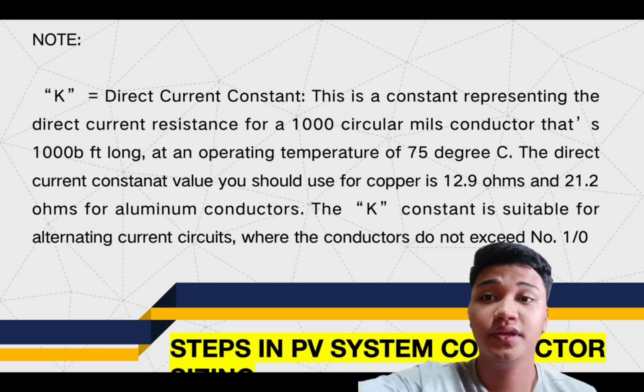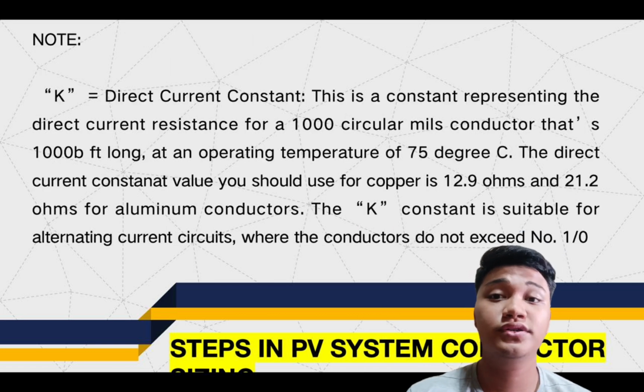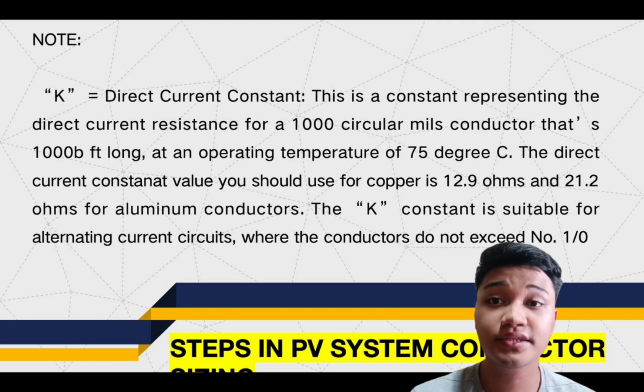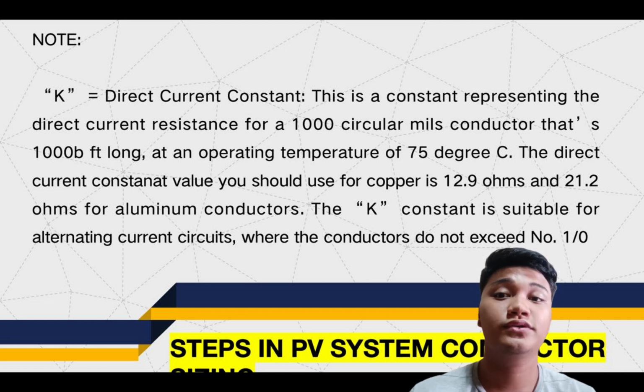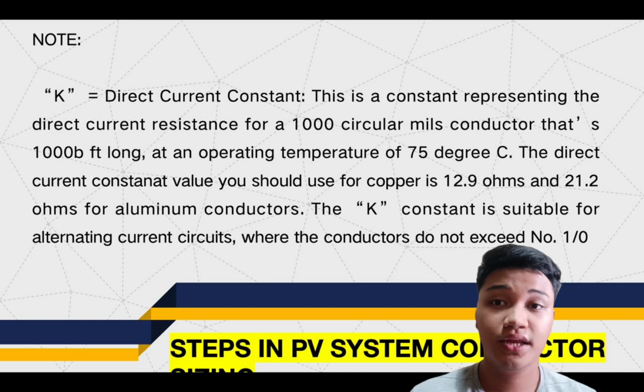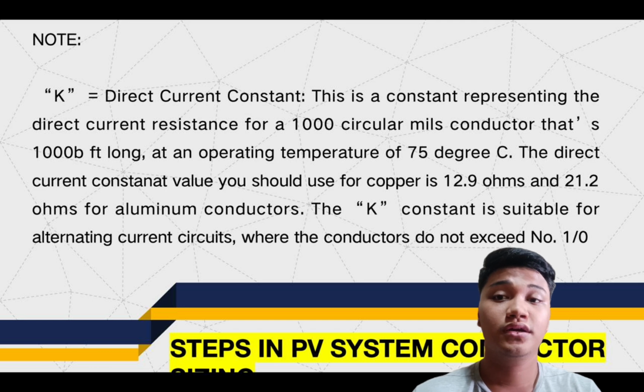Note that K, direct current constant, is a constant representing the direct current resistance for a 1,000 circular mils conductor that's 1,000 feet long, at an operating temperature of 75 degrees Celsius. The direct current constant value you should use for copper is 12.9 ohms and 21.2 ohms for aluminum conductors. The K constant is suitable for alternating current circuits where the conductors do not exceed number 1/0.